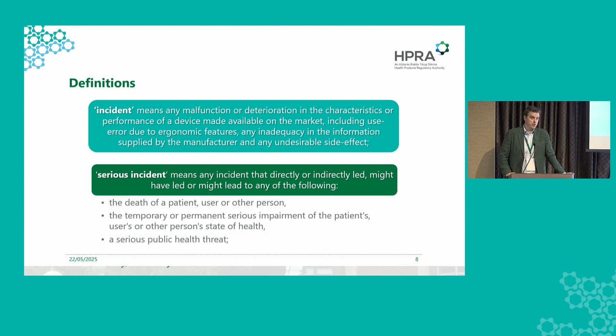So to assist the manufacturers in making this determination, the competent authorities have generated what we consider to be a quicker and easier way of applying a set of criteria to determine if there's a serious incident. I'm not sure manufacturers would agree with us. But the first is that an incident has occurred. And really that's, as I said, a device has failed to achieve its intended purpose. So the device in some way has failed.